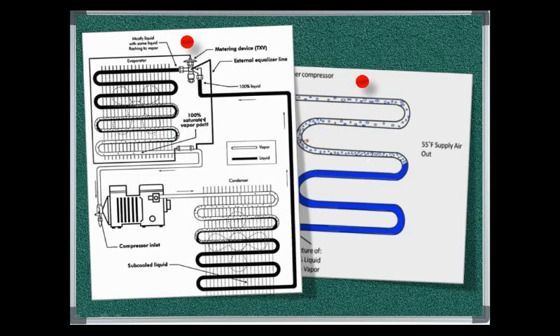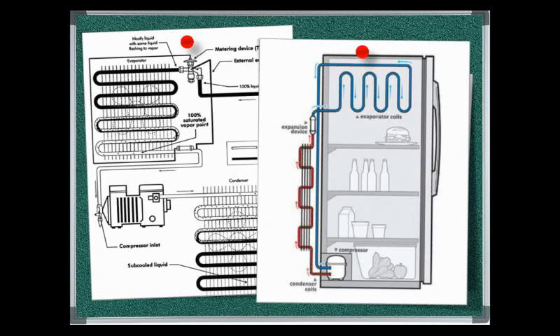This vapor state refrigerant is then absorbed by the compressor. The evaporator consists of finned tubes which absorb heat from the air blown through a coil by a fan. Fins and tubes are made of metals with high thermal conductivity to maximize heat transfer, and the refrigerant vaporizes from the heat it absorbs. In a domestic refrigerator, the evaporator is commonly known as the freezer. In window and split air conditioners, it is called the cooling coil. In large refrigeration plants and central air conditioning plants, it is known as the chiller, as these systems first chill water which then produces the cooling effect.